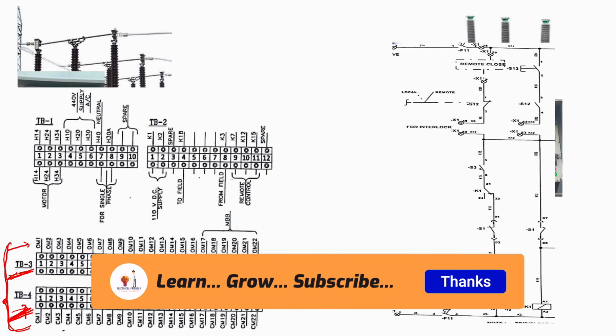Likewise, in the circuit breaker, this is the closing circuit diagram. This is the breaker closing circuit. Here you will get the closing coil. This is my closing coil. The negative will pass through here, from here through K1, through S3, and you will get a negative here. This is for interlock. You can read here, this is for interlock.